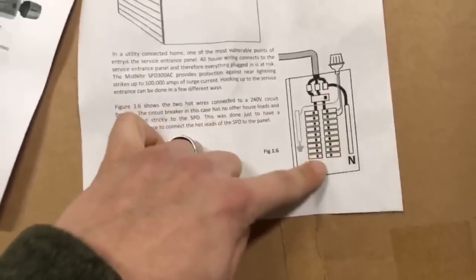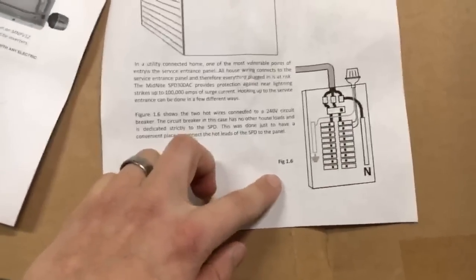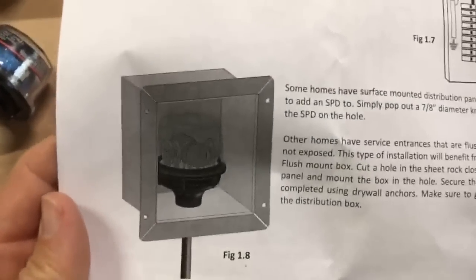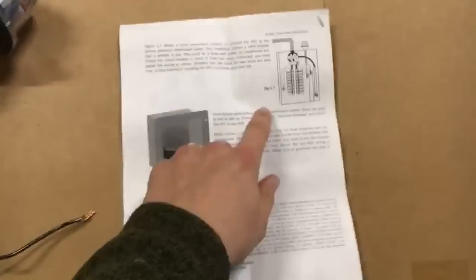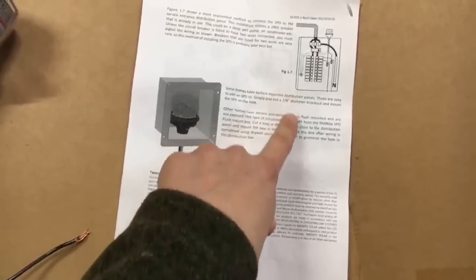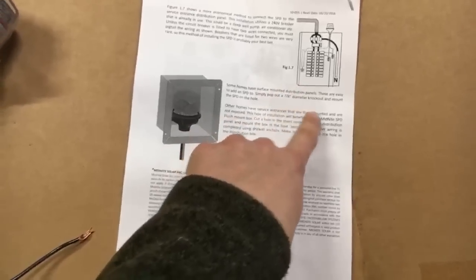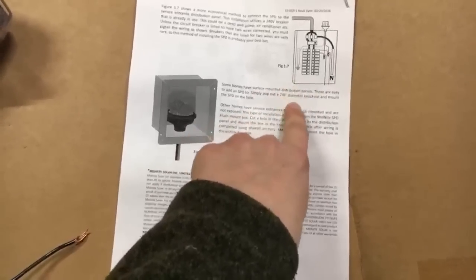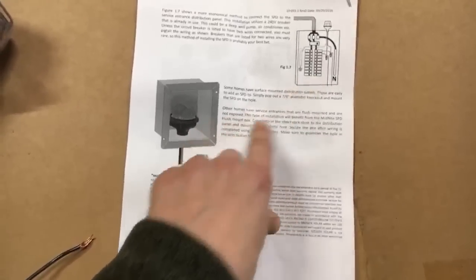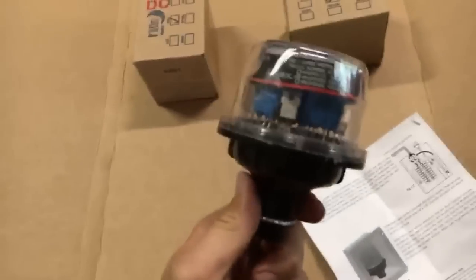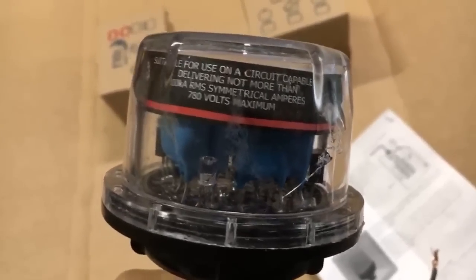I'll tell you a little secret trick too. A lot of times your electrical panel is recessed in the wall. There's a little box MidNite sells that you can install, but I'll just cut a hole underneath the panel, put in a piece of plexiglass, maybe add some trim, and screw the plexiglass on underneath. It looks really nice and you can see the surge protector. You want to call it a lightning arrestor so bad, but you're not supposed to—it's not a lightning arrestor, it's a surge protector.